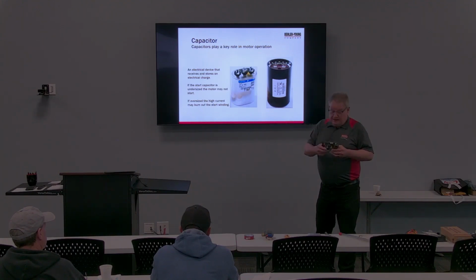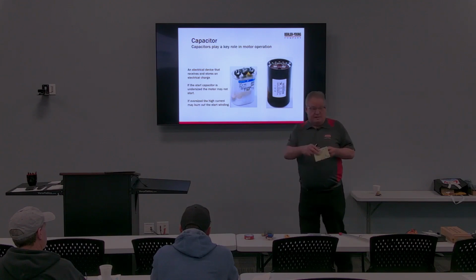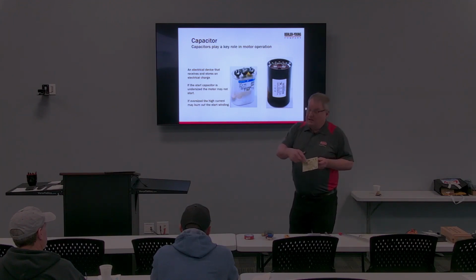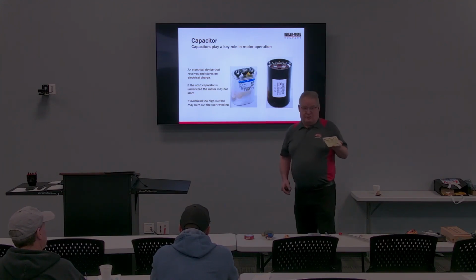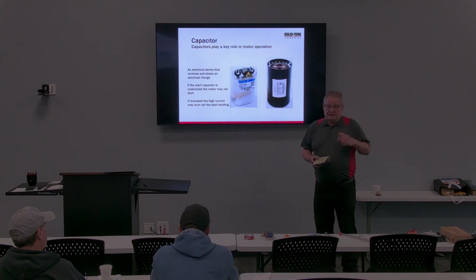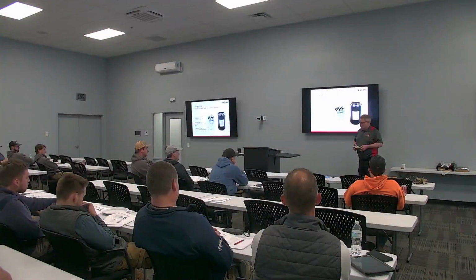Okay, and you want to make sure you give it a full 5 minutes before you start poking your hands around in there. And if you ever want to see something, you go to the back side of the capacitors and shut the power off, put your voltage meter there, set it to DC and go across those capacitors and watch how long it takes to discharge. DC volts is pretty dangerous, okay, because when it comes out, it grabs a hold of you and it holds on.